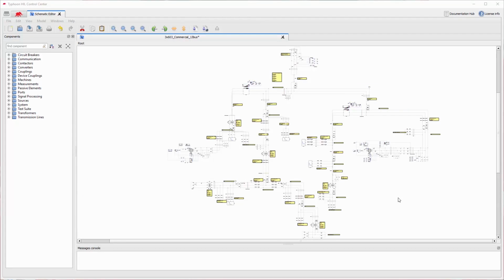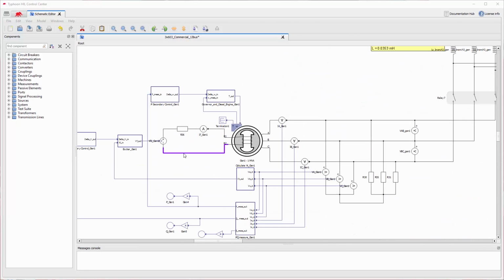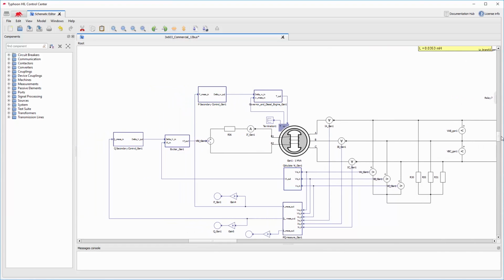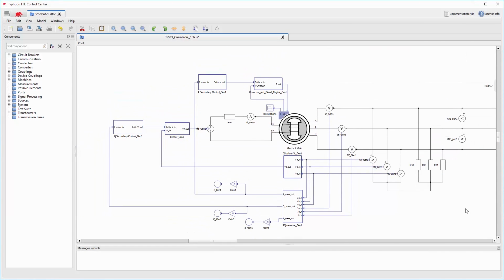In our software, the single line diagram is implemented as a 3-phase diagram and built with elements directly from our library. The diesel gensets are implemented as synchronous machines that have voltage and speed controlled respectively by an exciter and a governor in the primary loop. In the exciter loop, the voltage from phase to neutral of the 3 phases are measured at the point of connection with the grid, and the equivalent terminal voltage is calculated. This voltage is then sent as a feedback to the exciter that compares with the defined reference and applies a field voltage that will bring the terminal voltage to its desired set point.